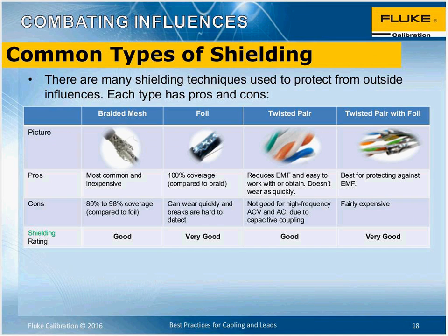The next slide is an indication, with some pictures, of what we've been talking about: braided mesh, foil, twisted pairs, and twisted pairs covered with foil. It's a bit of a summary to say, okay, there are these different types of shielding and different types of cables that can help us to avoid some of this pickup of unwanted signals getting into our measurement circuit, and also avoid some of the currents that might be flowing in our measurement leads getting out and causing problems as well.